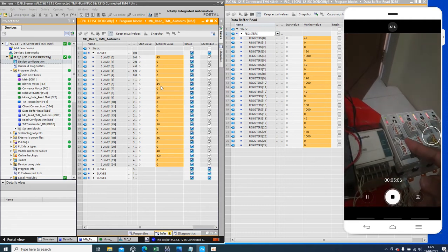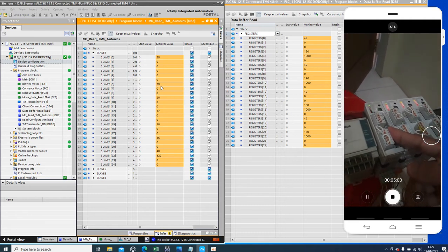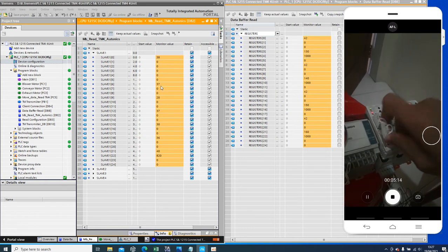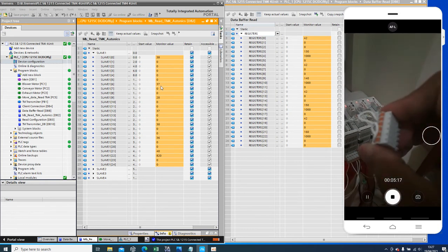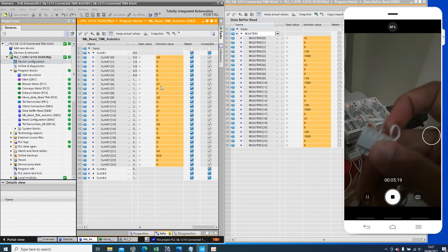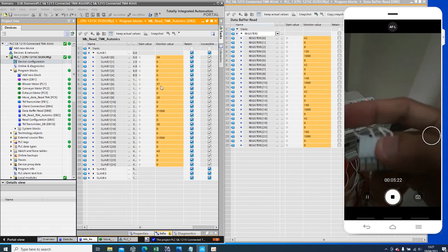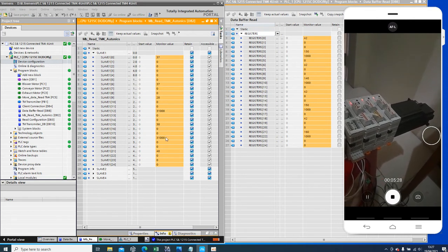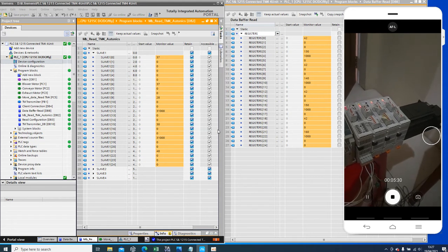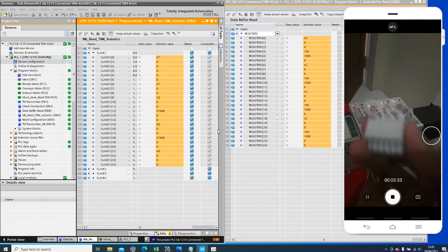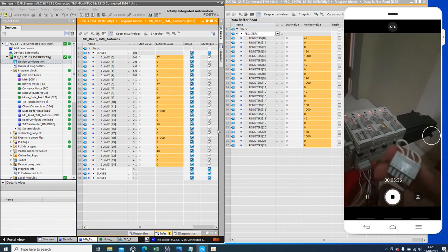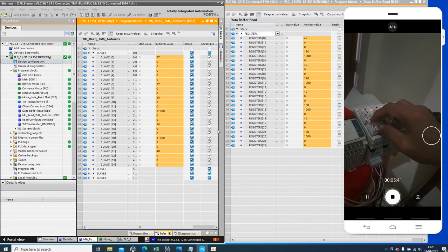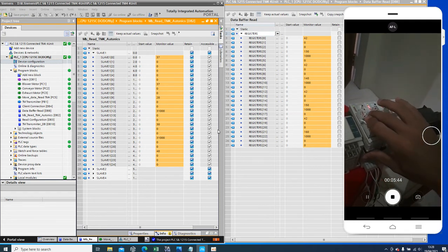If I take this connector from select one — I already took this. It means this is thermocouple 1 and thermocouple 2. You can see the actual temperature already changed, meaning it doesn't have a sensor. If I connect this connector to this module, the present value from the PLC will be changed.